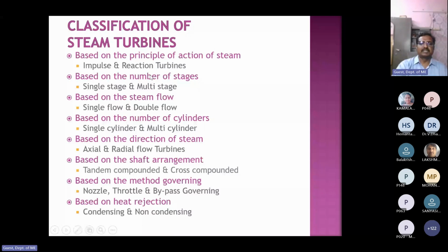Based on the number of stages, as I told, there are fixed blades and moving blades in the turbine. One fixed blade row and one moving blade row together are called a stage. So here in the HP turbine we have 25 stages. If you take the IP turbine, you have 20 plus 20, 40 stages. In the LP turbine, you have only 8 plus 8 stages.